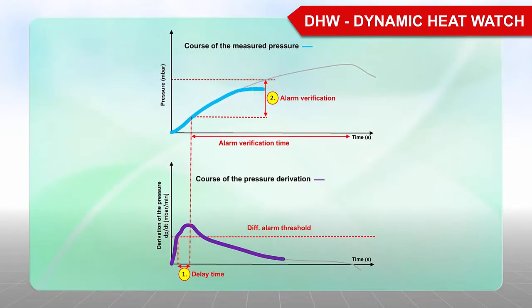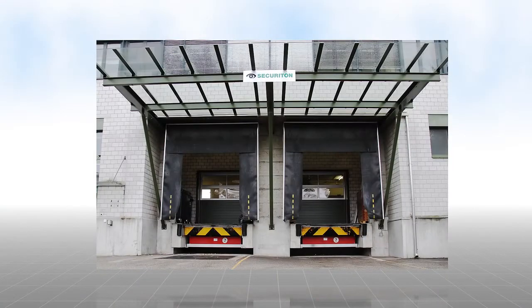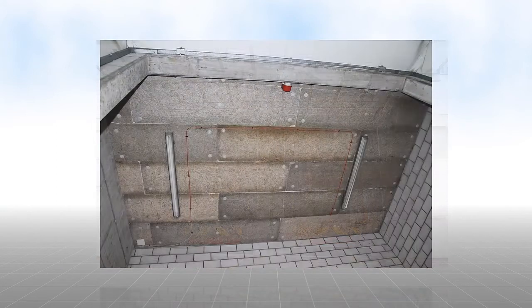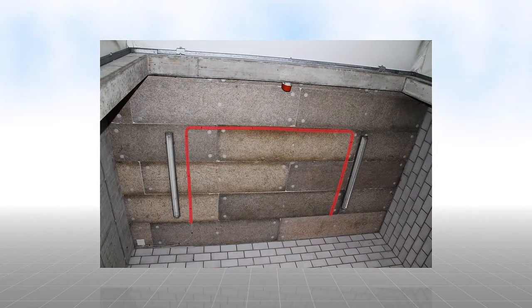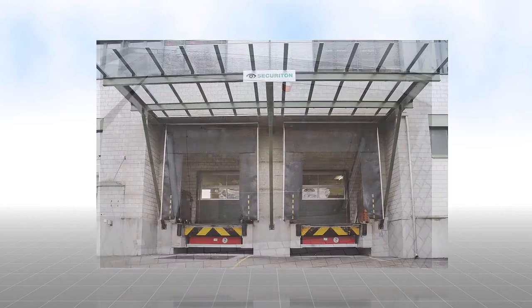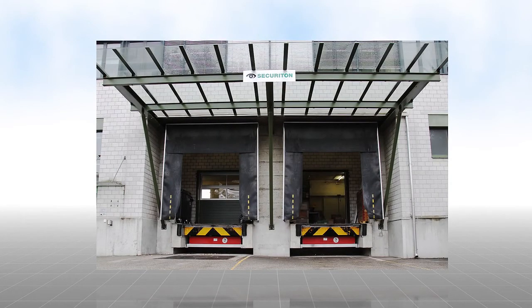If the ALARM VERIFICATION time expires without the expected pressure increase, then this is only a disturbance. This can be explained well using a loading platform as an example. The sensing tube is installed under the roof on the outside of the loading ramp. If a large door is opened in the winter, a rush of warm air hits the sensing tube and creates a rapid increase in pressure. Because the rush of air quickly disappears, the measured pressure decreases so that the alarm verification time expires without incident. No fire alarm is triggered.